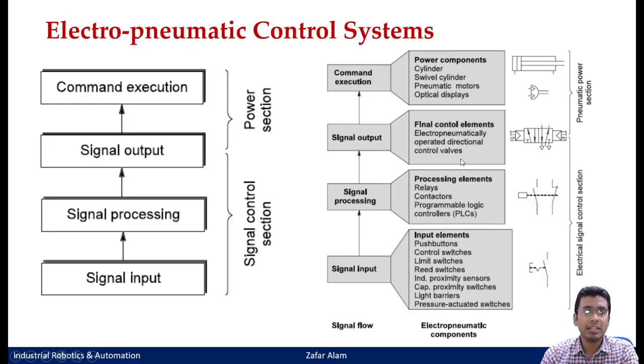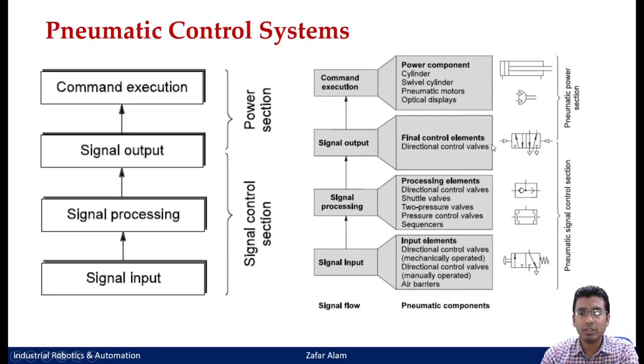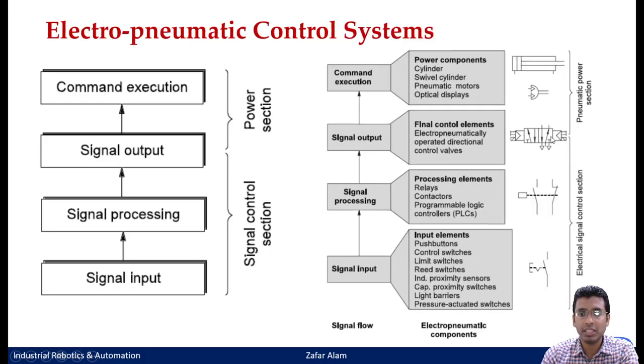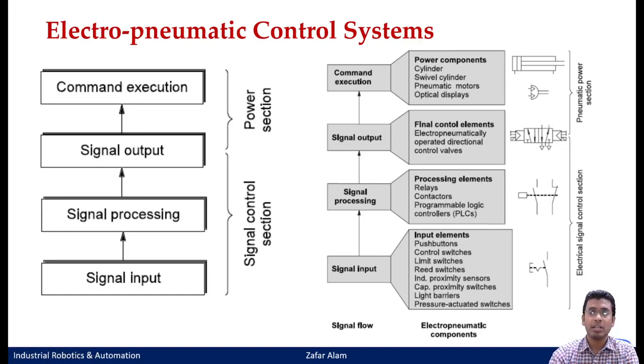Now compare this with an electro-pneumatic control. Even in the electro-pneumatic control, you will see a direction control valve, although in the earlier case it was a double pilot operated 5/2 DCV. In this case, it is a 5/2 DCV but it is a solenoid valve. All signals coming from the electro-pneumatic control system are electrical signals, which are processed and the output is an electrical signal that shifts the spool of the valve. The power section — cylinders and actuators — remains the same even in the electro-pneumatic section.